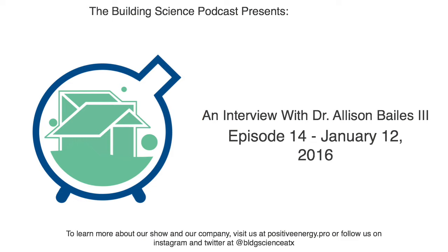A guy named Mike Barsick was one of the main guys behind that. He works at Southface. Really great guy. Anyway, in Georgia, we've had the blower door test required for 5 years now. Our threshold is relatively high, 7 ACH 50. So we probably could get some of that 3 CFM per 100 square feet back if a builder just passed that 7 ACH 50.